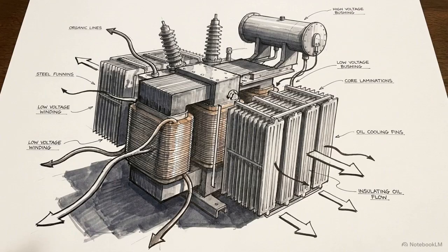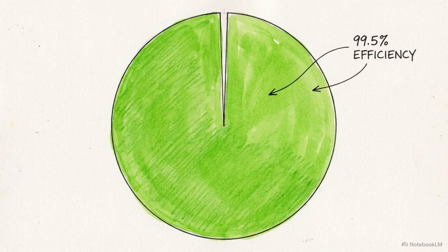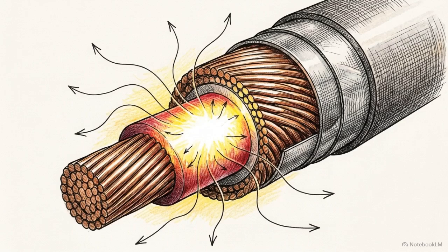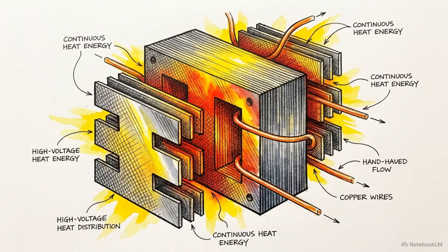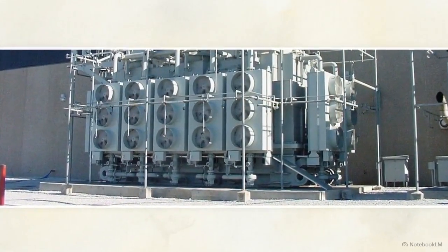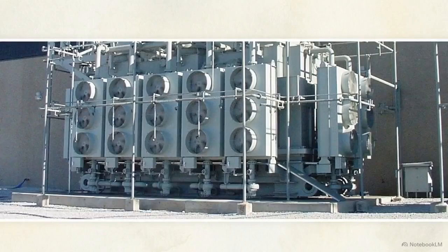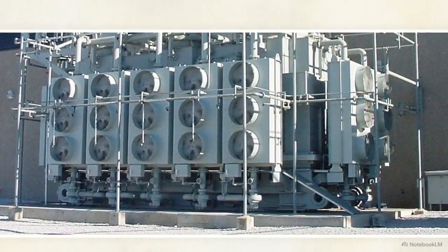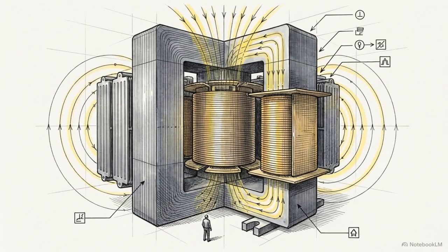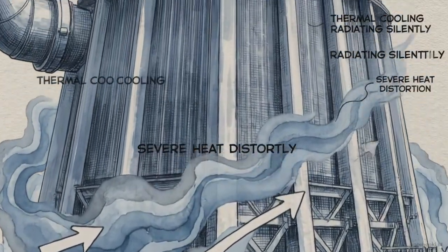Operating at this scale brings punishing realities. A 99.5% efficiency rating sounds virtually perfect, but if a transformer is pushing 100 megawatts of power, that tiny 0.5% of loss translates directly into massive, continuous heat radiating from the iron and copper. To survive, grid-scale units require dedicated pumps, oil radiators, and massive fans just to constantly flush that thermal energy out into the atmosphere. When you stand next to a grid transformer, its towering, house-sized footprint isn't housing moving gears. You are looking at the sheer volume of thermal cooling and electrical isolation required to safely contain megawatt-level energy.